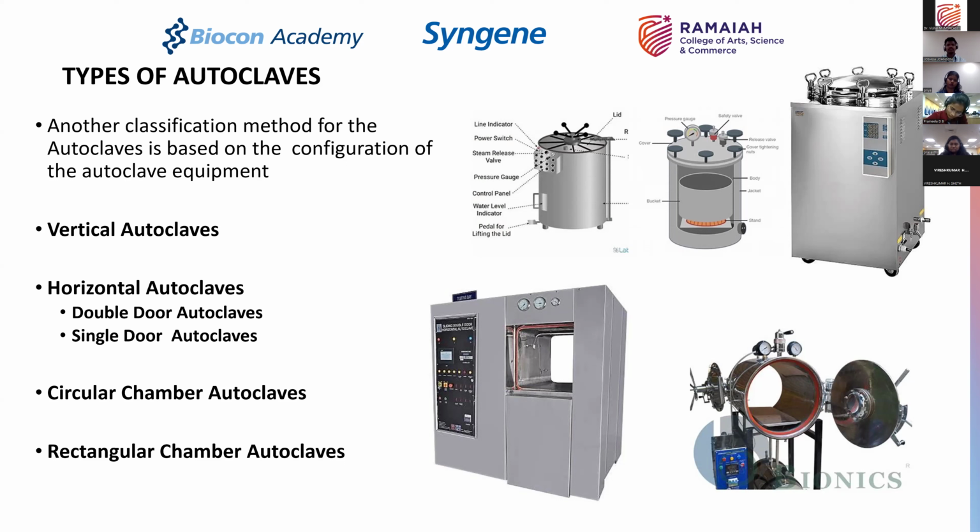But generally you would have a safety valve which goes off and releases the pressure, and it should give you an indication that you should cut off the supply. If you do not take care of that, then it will also fly off, right? I'm sure we have seen videos or have maybe experienced pressure cookers at home flying off also, because somebody forgot to put sufficient water into that. Therefore, the water content is important.